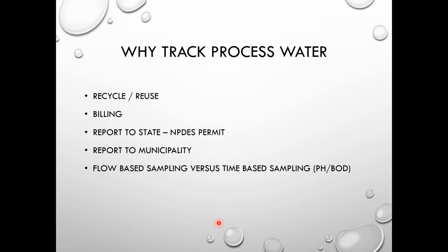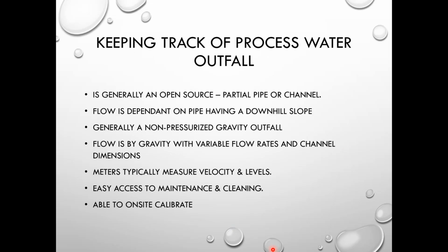And so I find it to be much more accurate if we can do a flow-based sample rather than a time-based sample. So essentially the flow meter will trigger the sampler every 100 gallons or 1,000 gallons, whatever you've got that set for, for an accurate grab sample. So keeping track of the process water outfall.